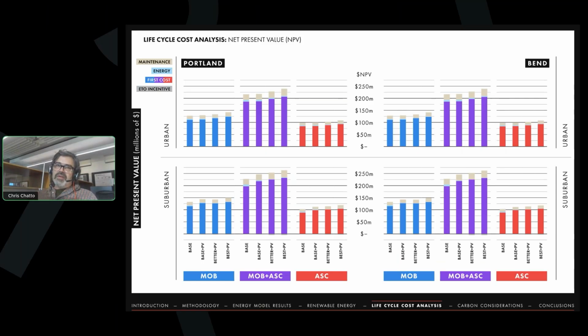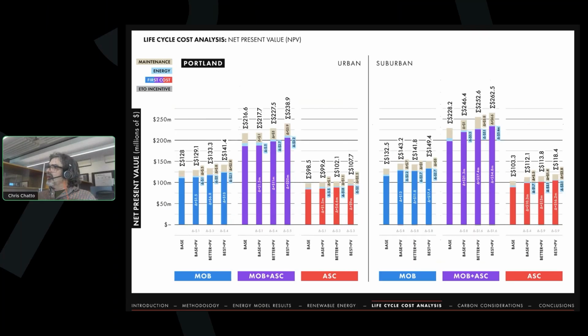You can also see that the annual maintenance cost is more than our energy costs, or more than our energy savings, which hinders us from paying back on those energy savings. That's driven by the fact that we have some of the cheaper commercial energy rates—we're blessed with that in the Pacific Northwest—which makes it more challenging in this typology, where we can't eliminate systems to achieve energy savings within these bundles as we've defined them.